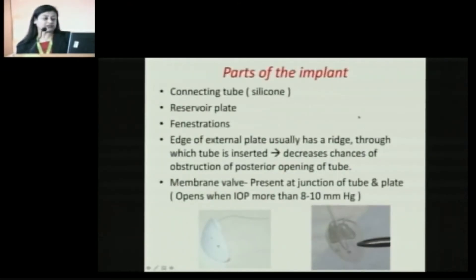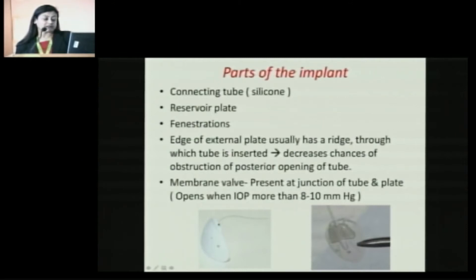What are the parts of these implants? Basically, whether it is a non-valved or a valved implant, there is a connecting tube which is made up of silicon. There is a reservoir plate. There are fenestrations and anchoring holes. The fenestrations are mainly to anchor with the fibrous tissue. At the edge of the external plate where the tube inserts, there is a ridge which decreases the chance of occlusion of the tube at that part. And in the valves, in this area, there is a membrane valve made up of silicon elastomers, which opens when the IOP rises more than 8 to 10 millimeters of mercury.